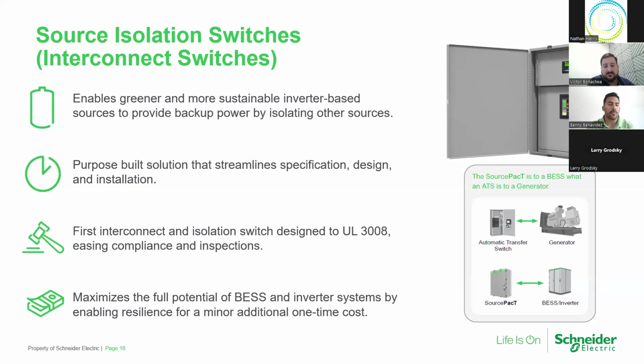So, source isolation switches. The product you see here in the top right is SourcePacT. It has a motorized breaker. On top of that breaker, it has a controller, and this device helps isolate safely from the utility to enable greener, more sustainable inverter-based sources to provide backup power. Now, this whole focus here, we're talking about enabling battery resiliency. That doesn't overlook the fact that we're talking about reliability in a different aspect. And if you're considering designing a microgrid system or incorporating energy storage, it's very important to also consider reliability, right?